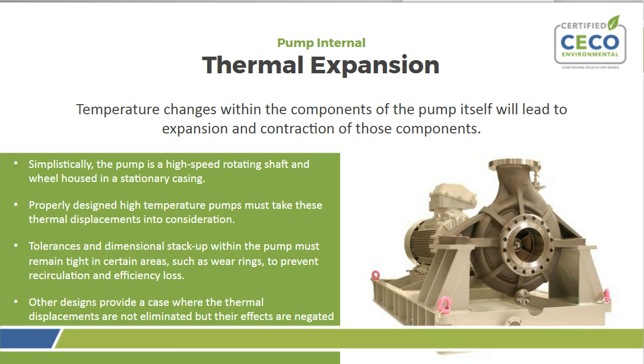But then for the other considerations, other designs provide a case where the thermal displacements are not eliminated, but their effects, in essence, are negated. So those are the different design aspects of the pump itself that we can include that basically negate the thermal displacements that the pump makes.